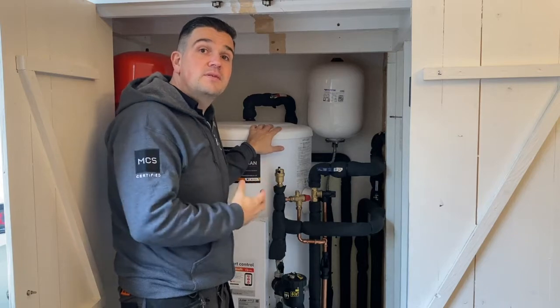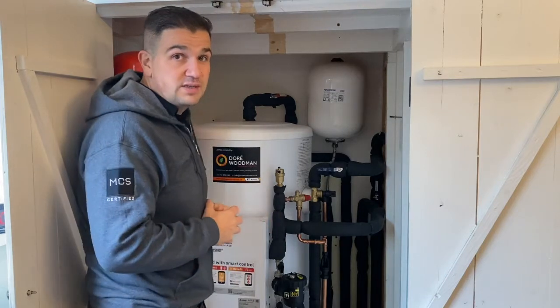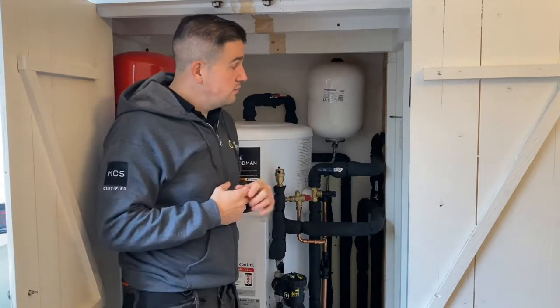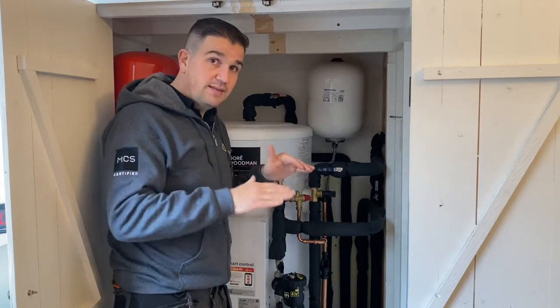With a pre-plumbed Doré Woodman hot water cylinder in place as well, this airing cupboard actually gives us good space to work with. We've got one heating zone on here, so we've got a radiator system and we've set the heat curve to provide around 45 to 50 degrees between those marks.